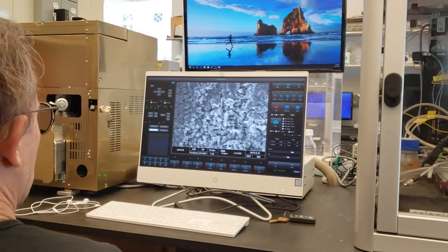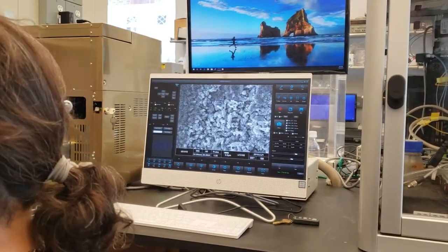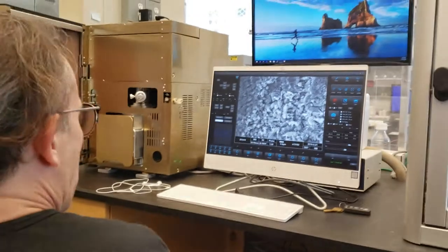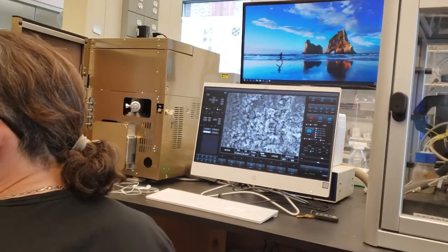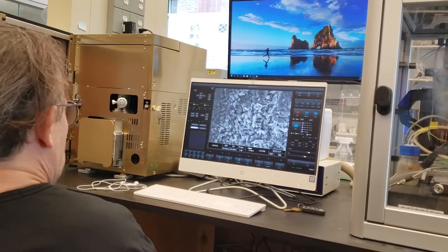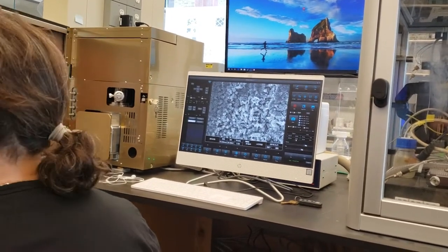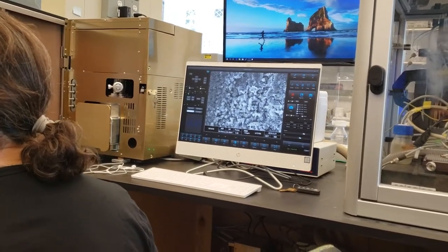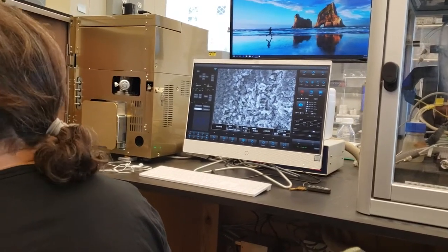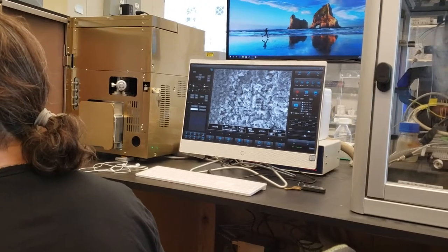Okay. Well, that brings up the question: when you tilt it, what kind of working distance are you looking at? Whatever this will read, it'll still be 10, you could raise it up to 10 or whatever. You can still do that, but let's say the focus says 11 and this will say 10, so just know that you're 1 millimeter off. It depends on where you look. If you look at the top of the grid, this might be 8.